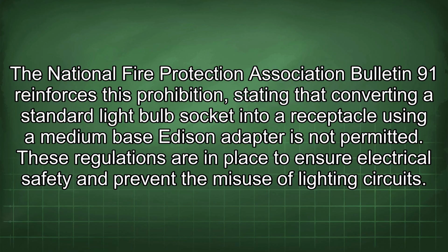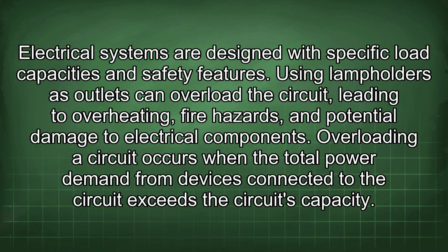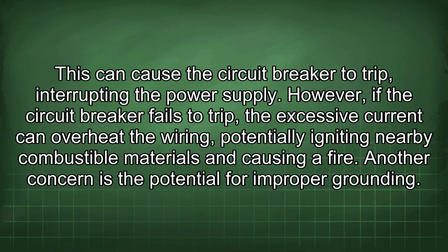These regulations are in place to ensure electrical safety and prevent the misuse of lighting circuits. Electrical systems are designed with specific load capacities and safety features. Using lampholders as outlets can overload the circuit, leading to overheating, fire hazards, and potential damage to electrical components. Overloading a circuit occurs when the total power demand from devices connected to the circuit exceeds the circuit's capacity. This can cause the circuit breaker to trip, interrupting the power supply. However, if the circuit breaker fails to trip, the excessive current can overheat the wiring, potentially igniting nearby combustible materials and causing a fire.